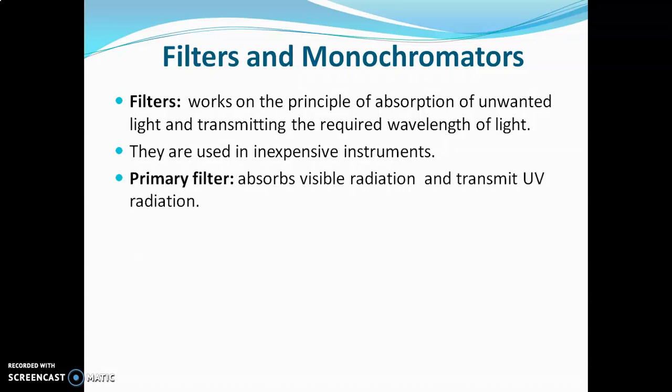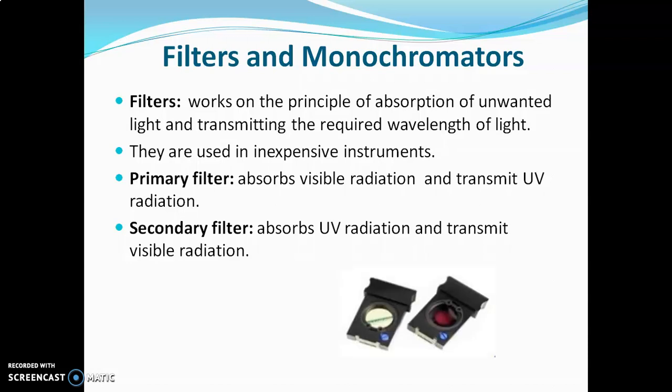Filters work on the principle of absorption of unwanted radiations and transmitting the required wavelength of light; such filters are known as absorption filters. Filters are used in inexpensive instruments. There are two types: primary filters, which absorb visible radiation and transmit UV radiations, and secondary filters, which absorb UV radiation and transmit visible radiations. Both types of filters are present in a fluorimeter.